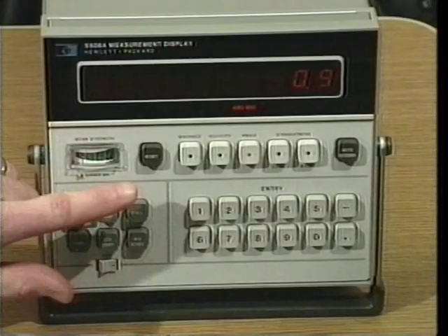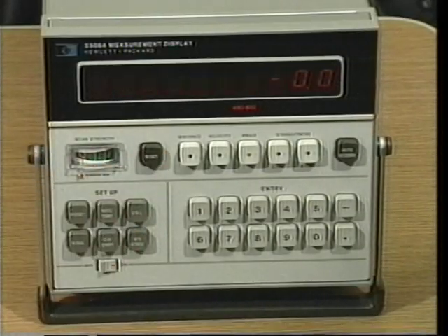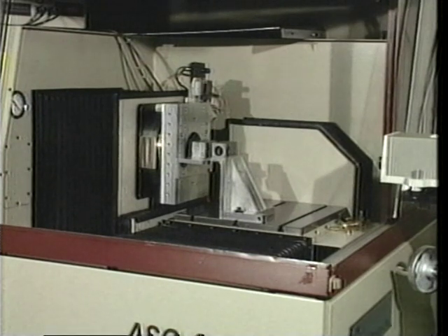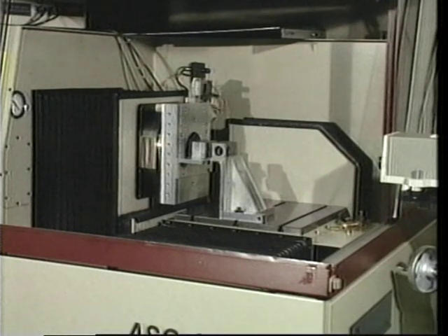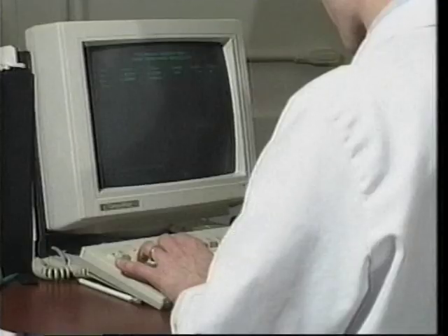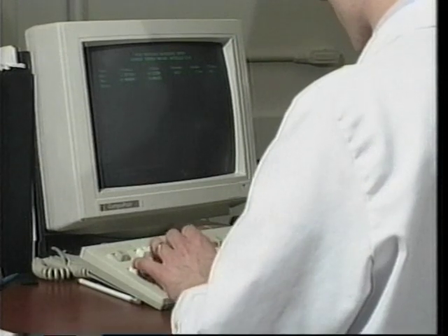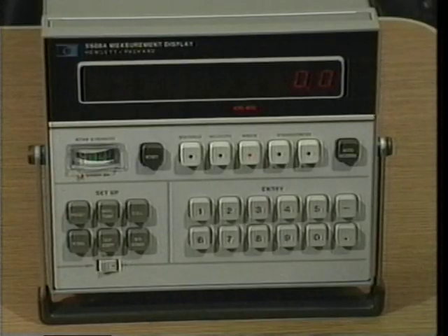To begin a measurement, the measurement display is reset to 0 with the reflector and interferometer at their minimum separation distance. In this case, that correlates to a z-axis position of z=0. The DTM is programmed to move the z-axis carriage from z=0 to z=150 millimeters in 25 millimeter steps. A 5-second pause between steps has been included to allow time for the carriage vibrations to diminish and the measurement display to stabilize. 0, the yaw angle reading for z=0, is recorded.